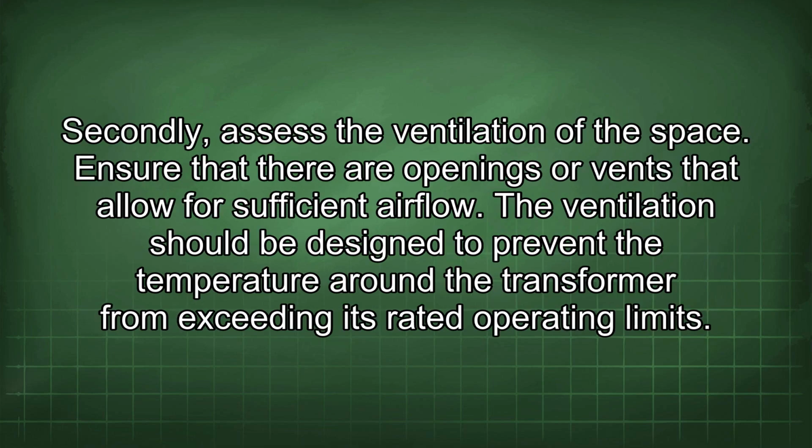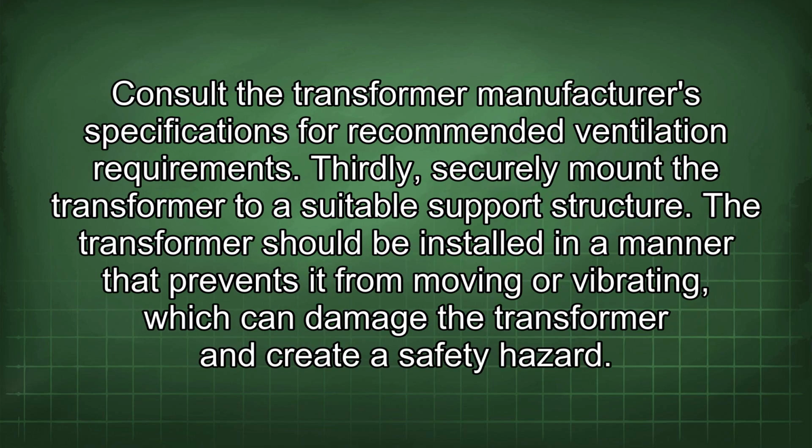Secondly, assess the ventilation of the space. Ensure that there are openings or vents that allow for sufficient airflow. The ventilation should be designed to prevent the temperature around the transformer from exceeding its rated operating limits. Consult the transformer manufacturer's specifications for recommended ventilation requirements.